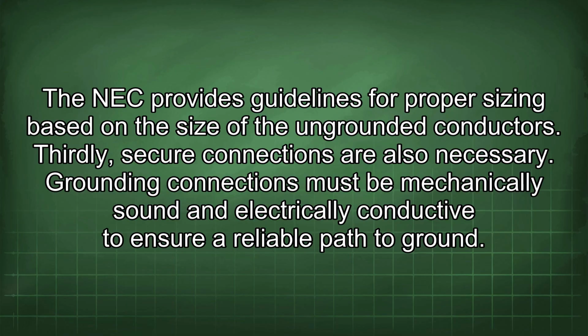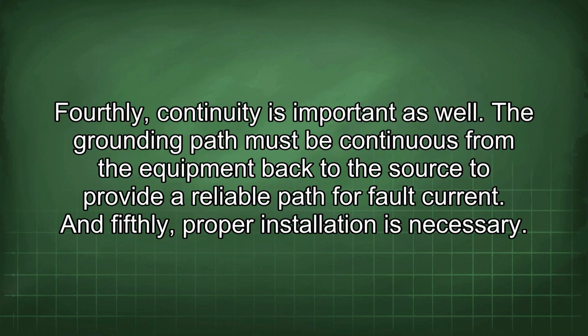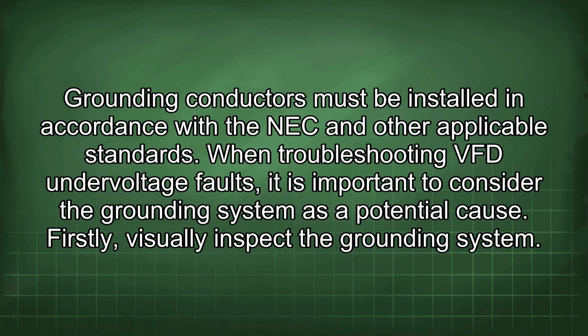Thirdly, secure connections are also necessary. Grounding connections must be mechanically sound and electrically conductive to ensure a reliable path to ground. Fourthly, continuity is important as well. The grounding path must be continuous from the equipment back to the source to provide a reliable path for fault current. And fifthly, proper installation is necessary. Grounding conductors must be installed in accordance with the NEC and other applicable standards.